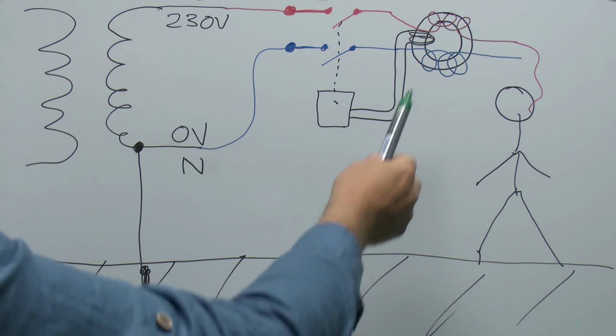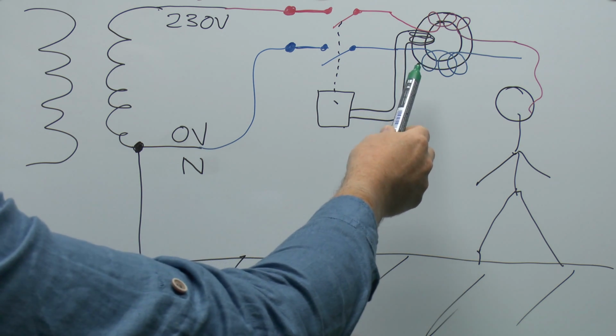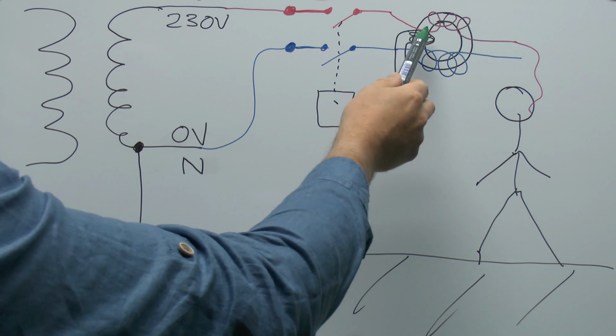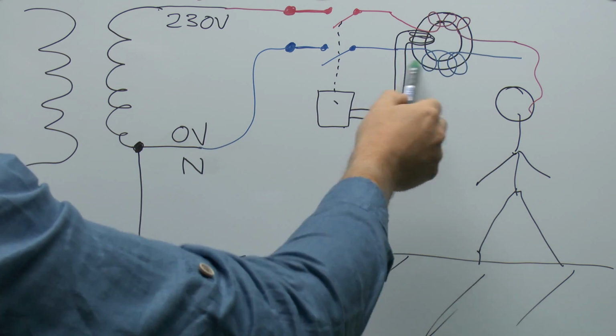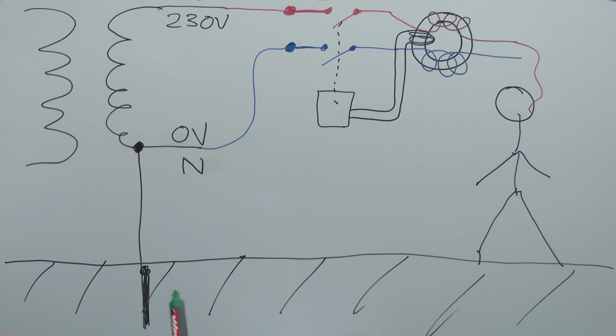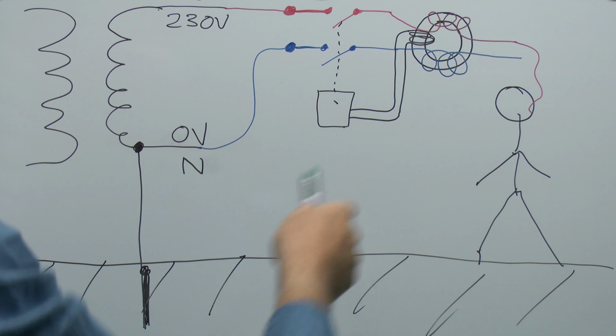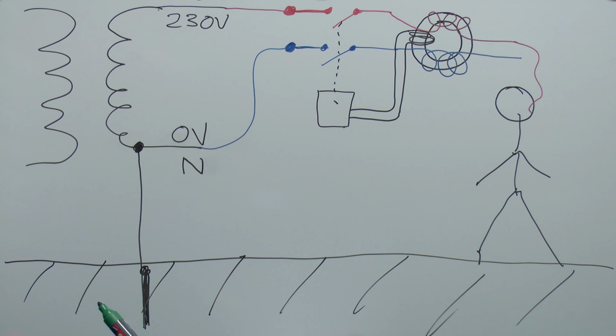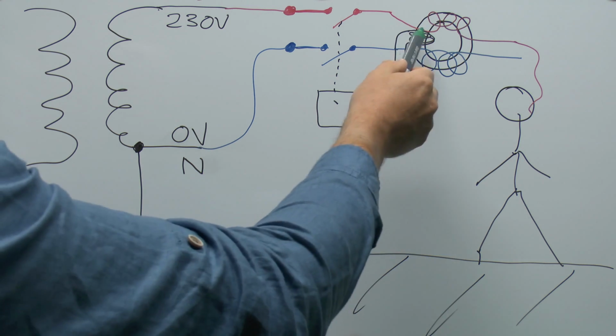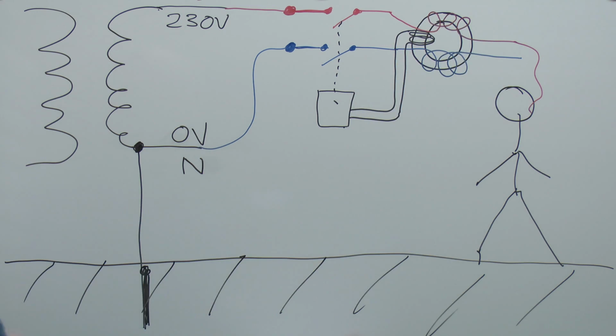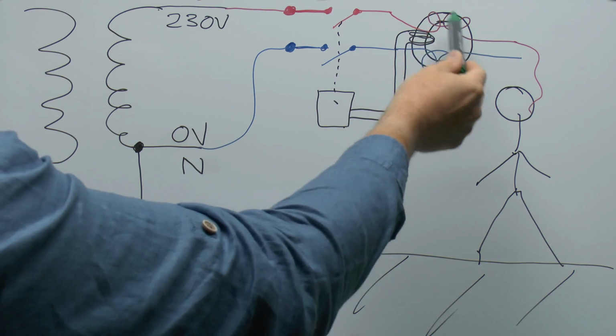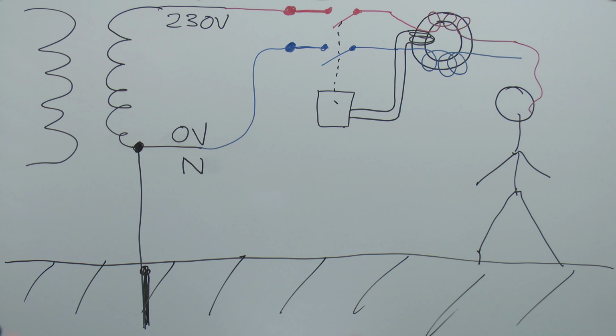Now, at one point there were actual RCDs made in this fashion, but there's a significant problem with this, because it means that the wires going into the coil here, and obviously on the return, have to be sized to carry the full load of whatever is actually going through here at all the time. And of course, if it's a fairly moderate size RCD, say 40 or 50 amps, these wires in the coil have got to carry 40 or 50 amps pretty much indefinitely.